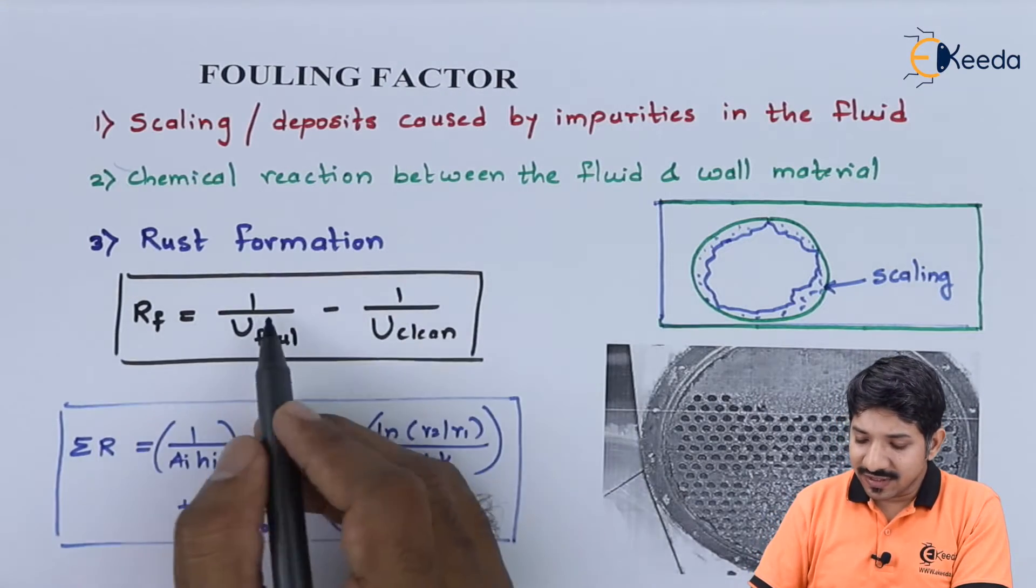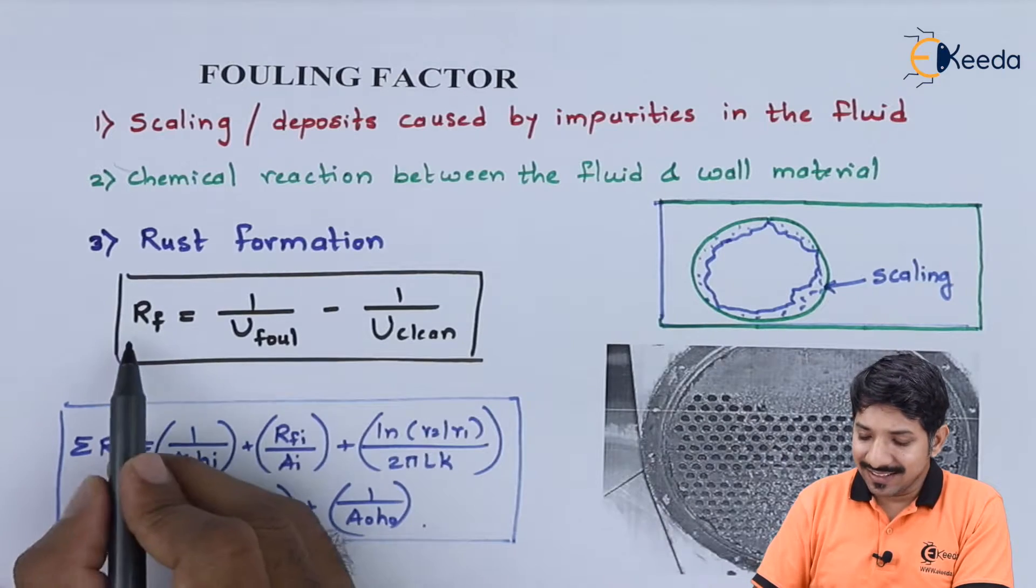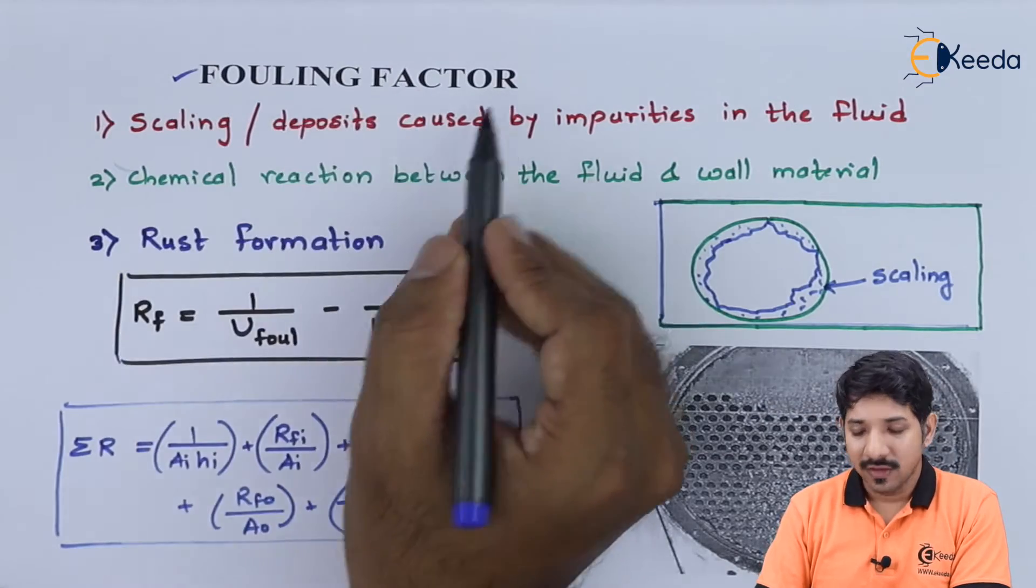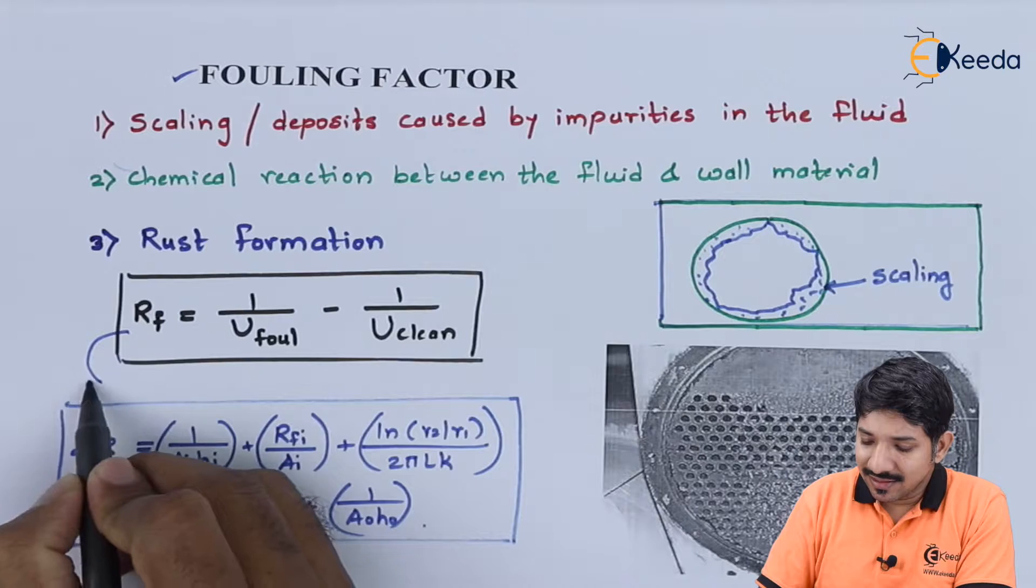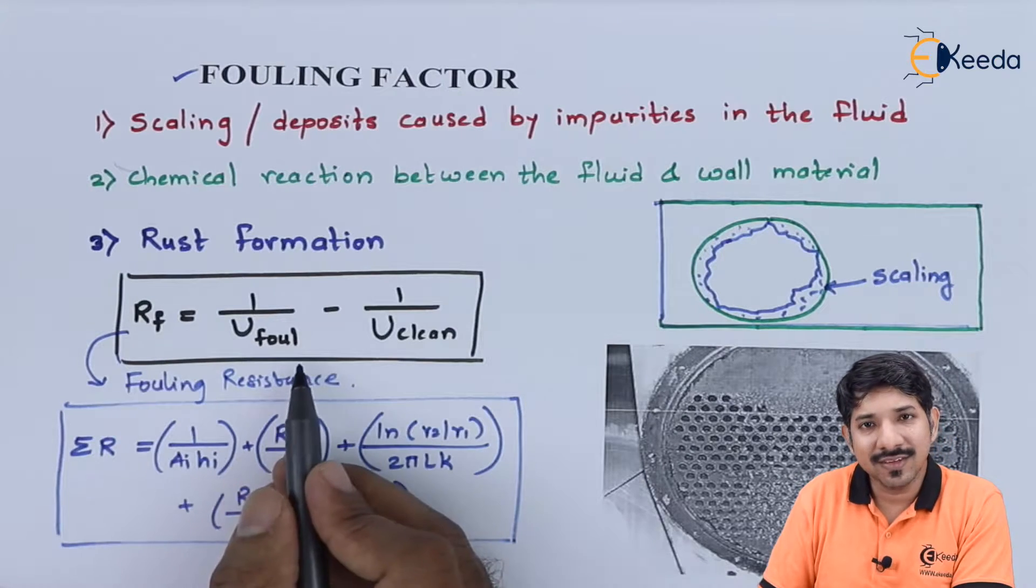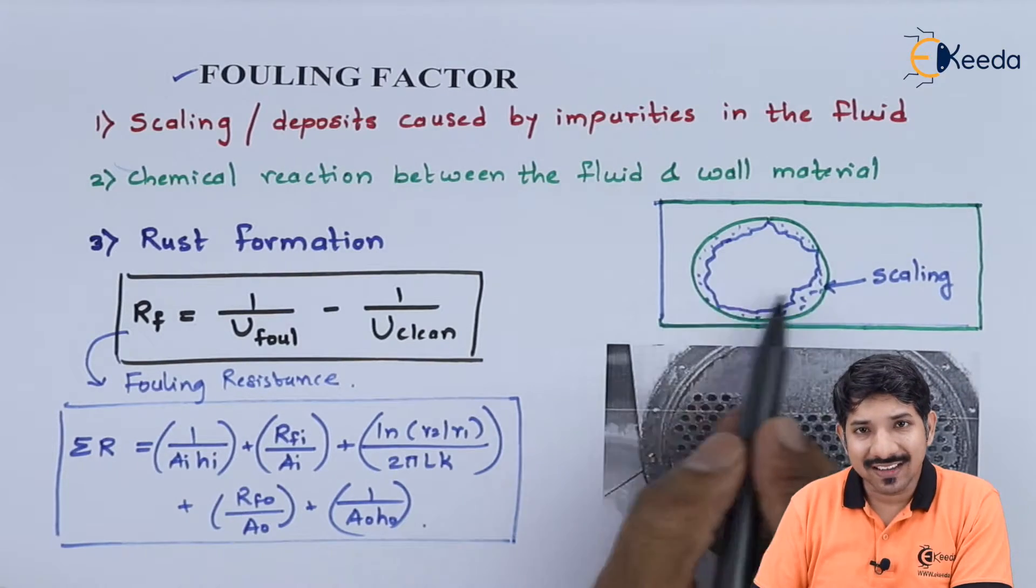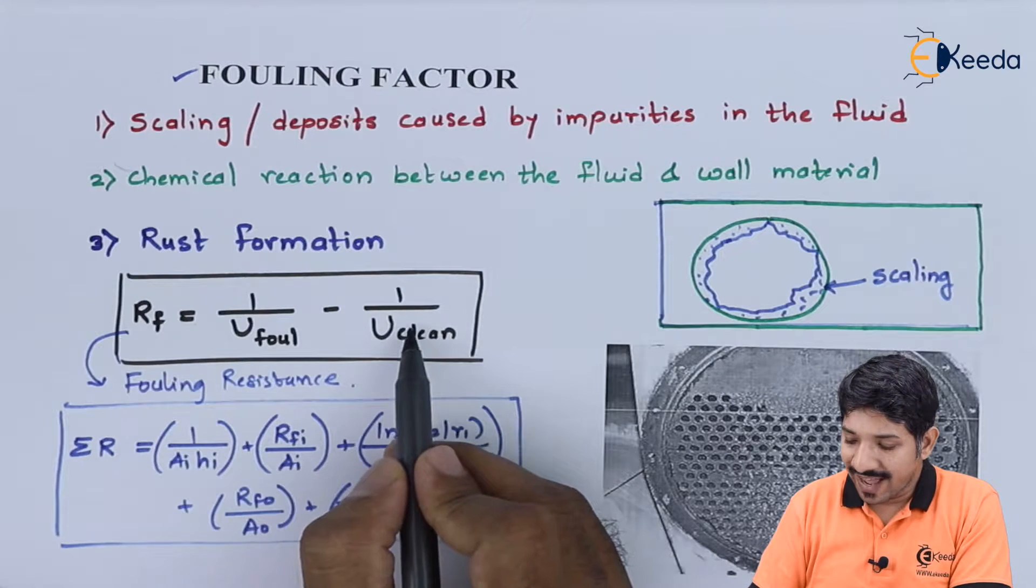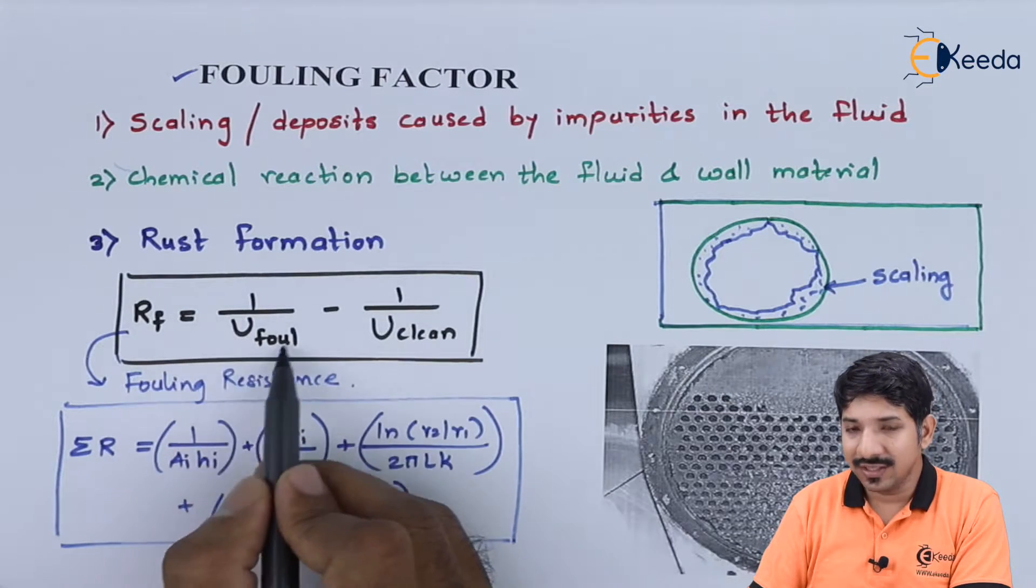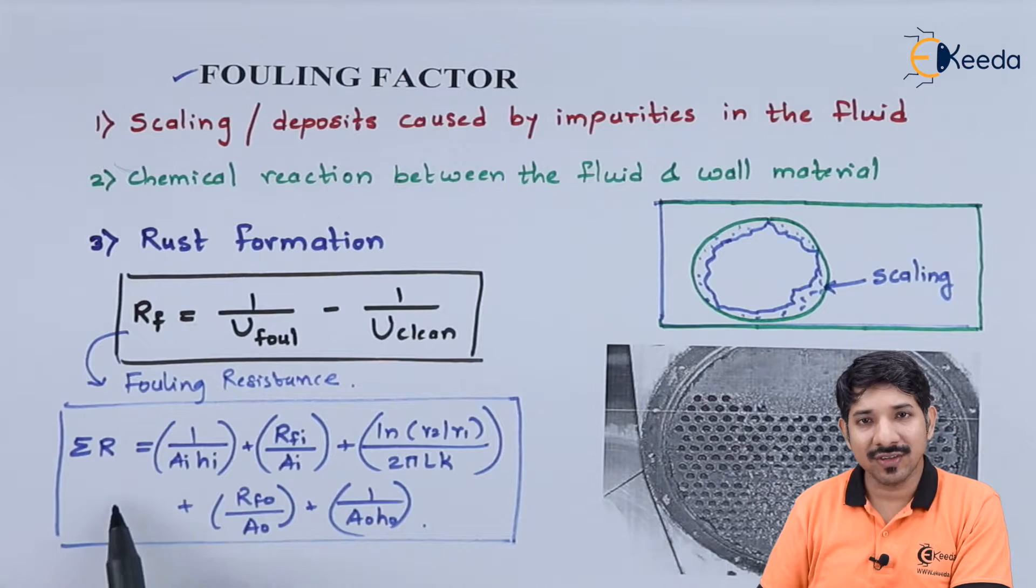So what happens because of this? A thermal resistance is created due to this scaling. Now, this resistance that is created requires us to consider a factor called fouling factor. This fouling resistance is calculated by finding the overall heat transfer for the fouled section and for the clean one. We need to find the U value initially in the manufacturing state and then in the maintenance state.